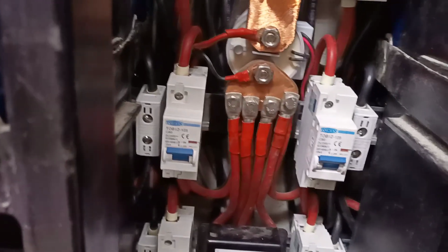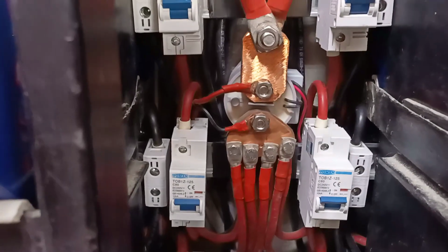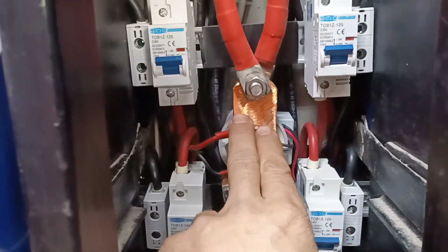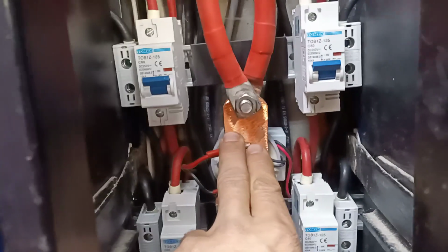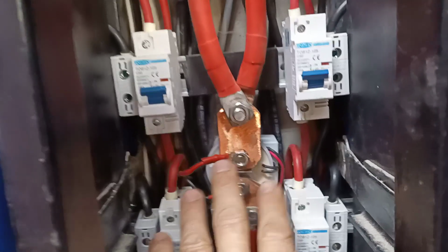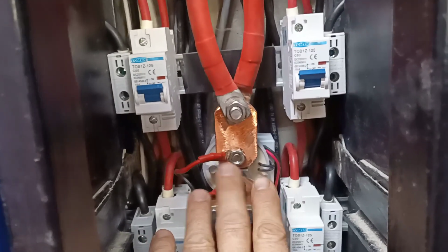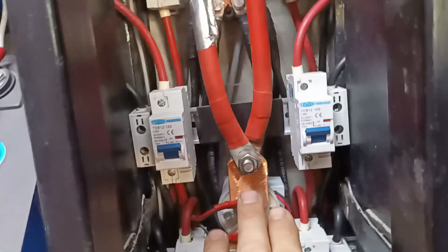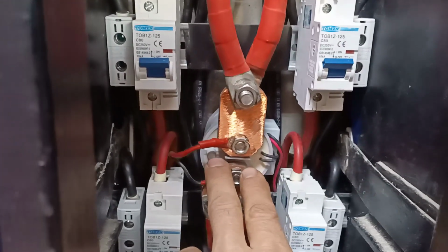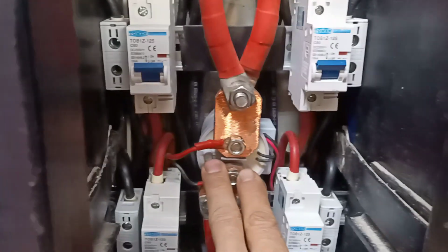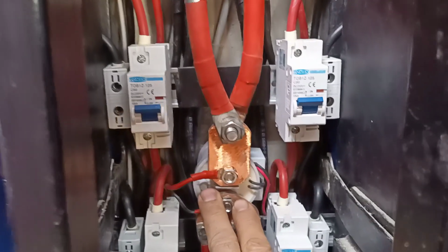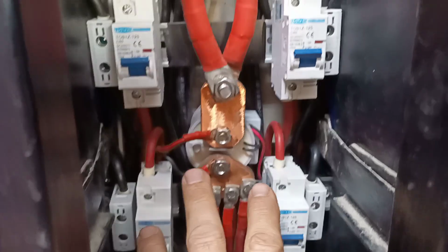I did break the weld by banging the contactor a few times on the ground, but the contactor stopped working properly. It was heating up a lot. But that's actually also useful information, because if the contactor is not working properly, it will heat up, and it will heat so much, over 100-150 degrees Celsius, that it can start a fire or something.